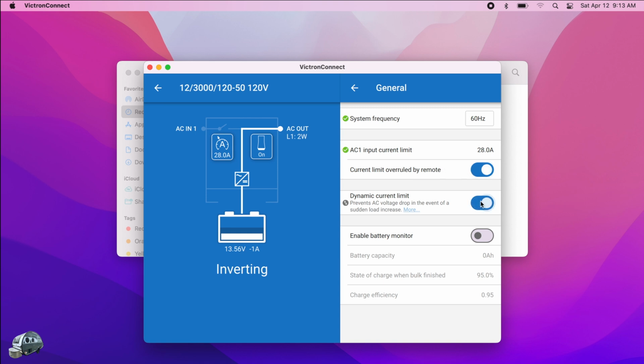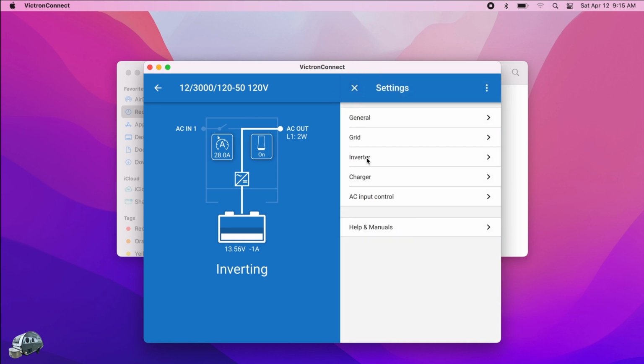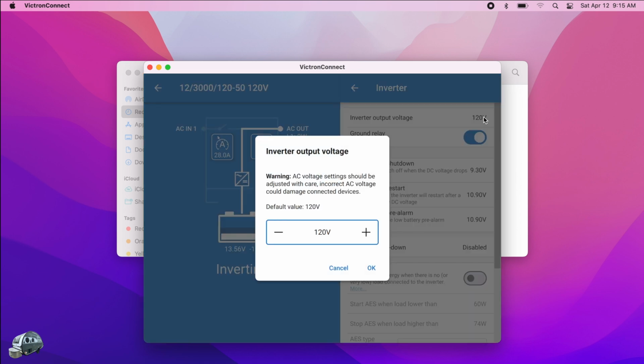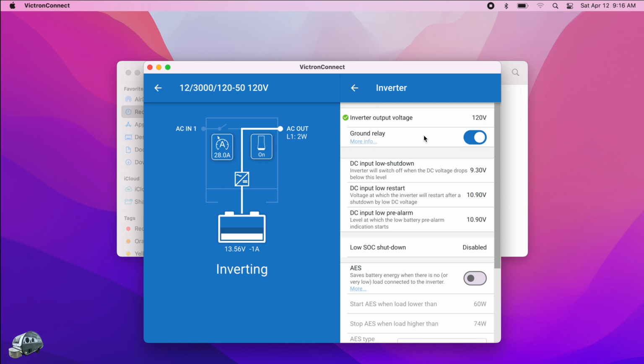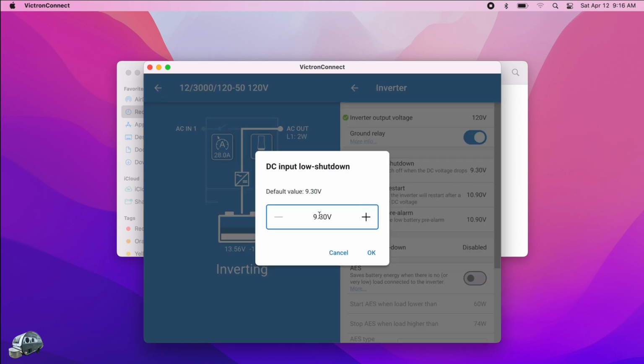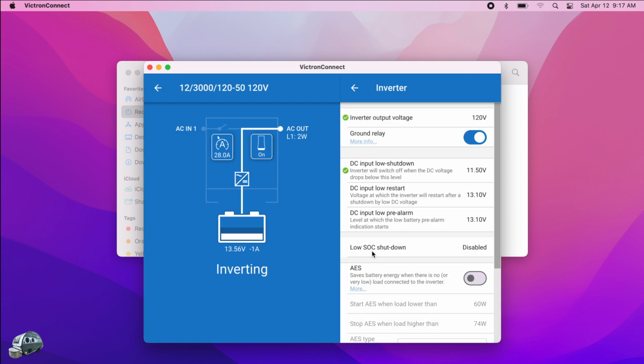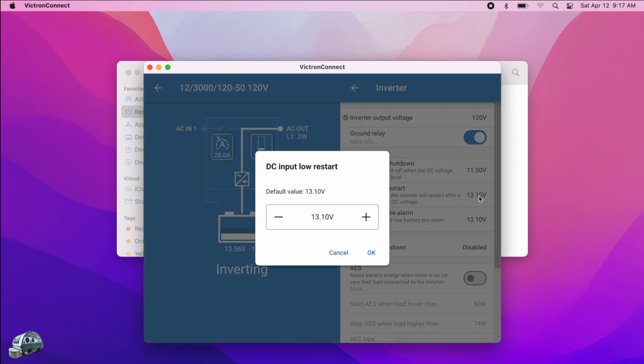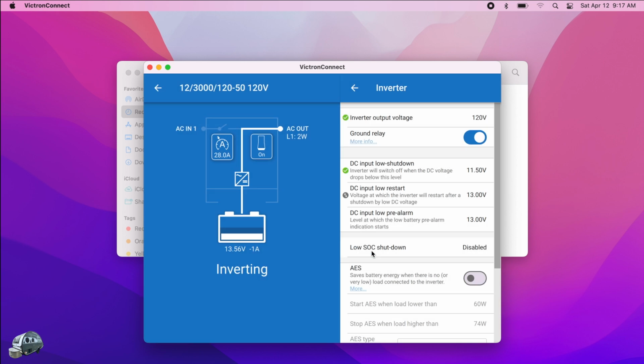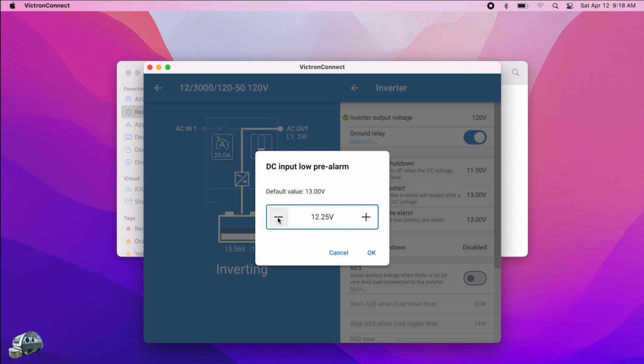Turn Dynamic Current Limit on. Select Inverter. Make sure the inverter output voltage is set to 120 volts. Change the DC input low shutdown voltage to 11.5 volts. Then change DC input low restart to 13 volts. Change the DC input low pre-alarm to 12 volts.